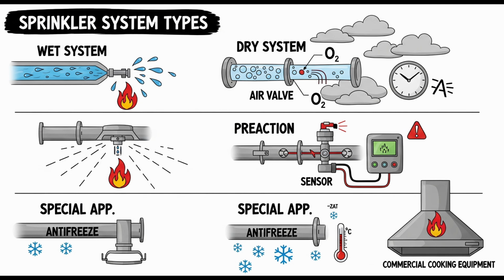That is a fascinating detail. A tiny vent to prevent seemingly small issues that can have big impacts. Wow. It really highlights the depth of consideration in the standard. Even the most basic system has these engineered nuances. All right, let's transition to systems where freezing isn't just a potential problem, but the default environment. Dry pipe systems. Okay. Dry pipe systems are designed specifically for unheated areas subject to freezing. Places like unheated warehouses, attics, parking garages. Loading docks and cold climates, exactly.